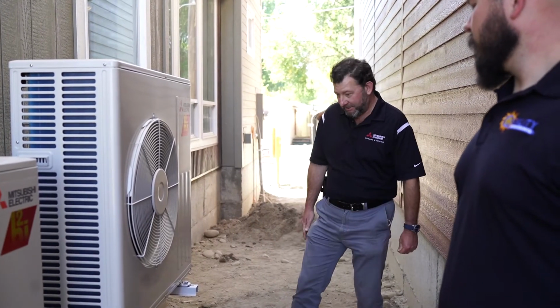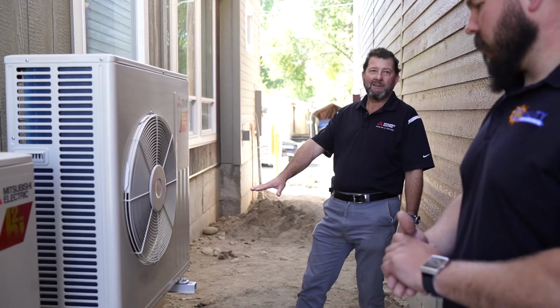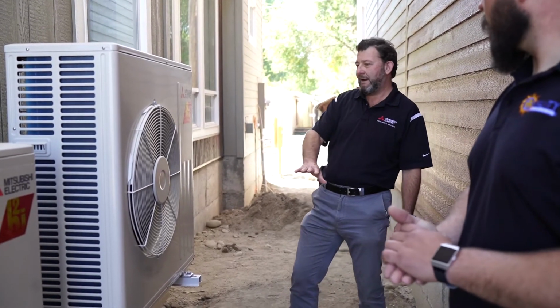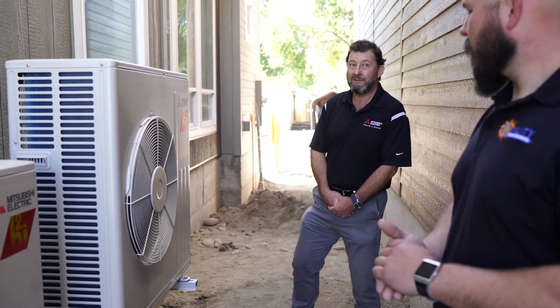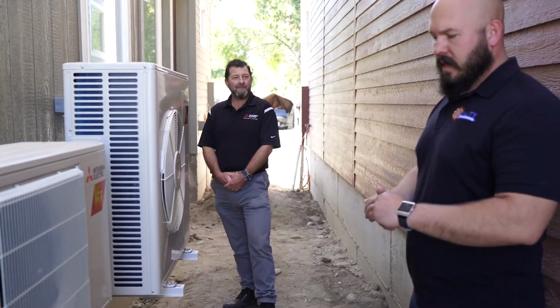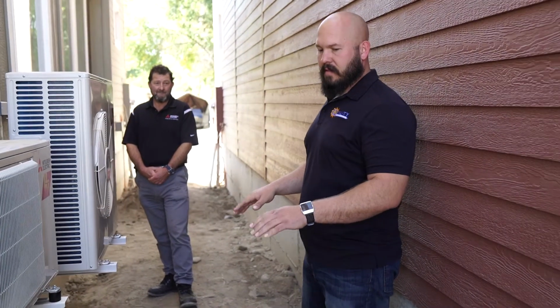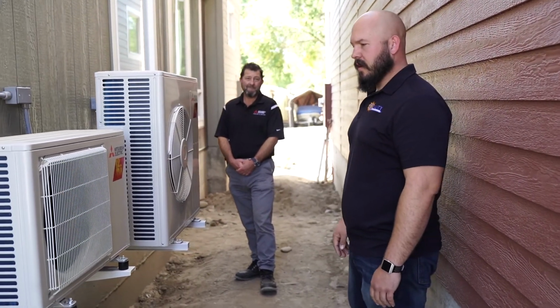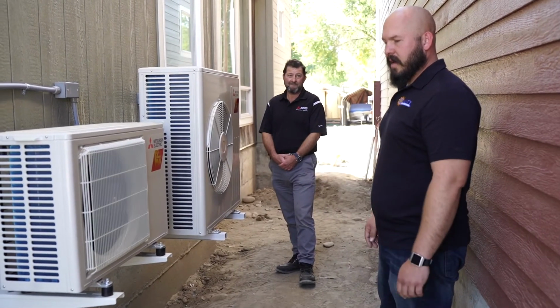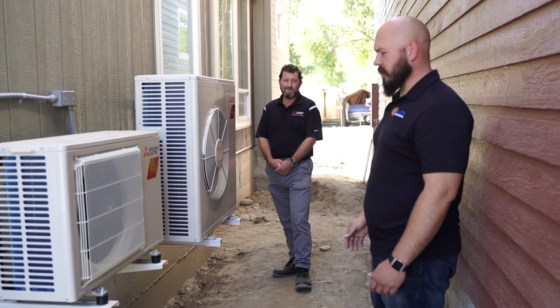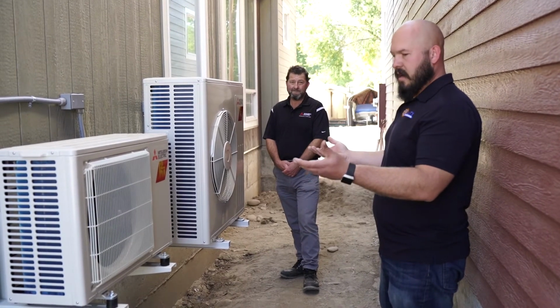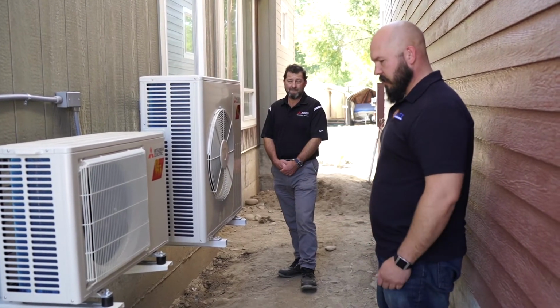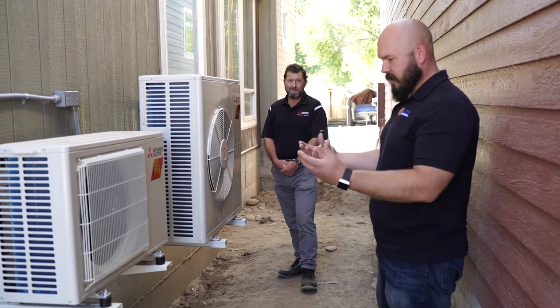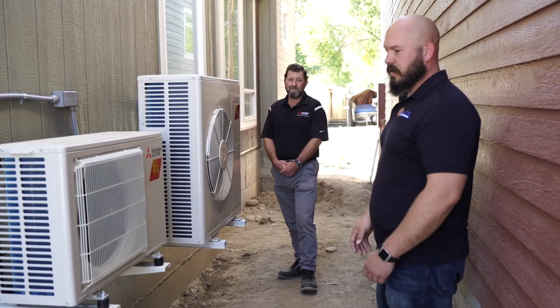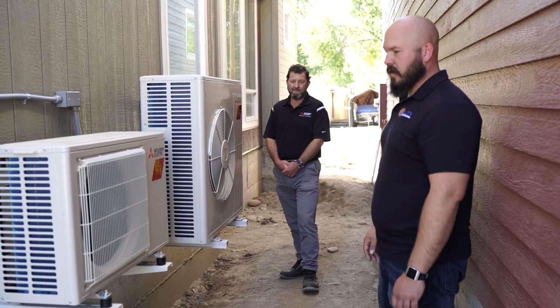Jordan, you do a really nice job installing these up off the ground, above the highest level the snow could reach. Do you want to talk about the importance of getting this higher than the snow and why we do that? In our area, I believe it's 6 inches they want us to maintain off the ground for snow load typically. Four or five years ago we had about a foot to 16 inches of snow constantly, so our idea is to keep this off the ground—I think we're at about two feet here. These do drain, so you want to keep ice and snow away from the units; all of that can damage it.